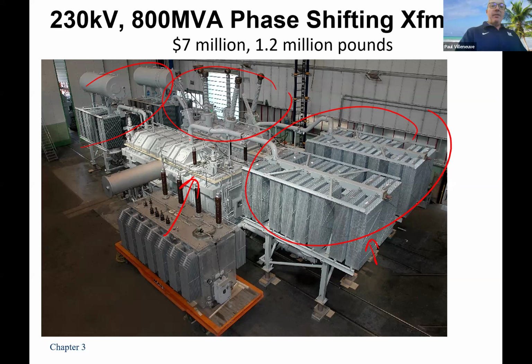And then the loop just keeps going all over again. You'll notice the pipe goes onto the top, right? So the hot oil goes in over here because it's lower density, and the cold stuff, kind of hard to see, there's a pipe that goes into the bottom. And so it just uses natural circulation to keep it cool. They do have, but not very common, forced oil cooled transformers where you actually have a pump that circulates the oil, which does a really good job for heat mitigation, but there's a huge problem with that.